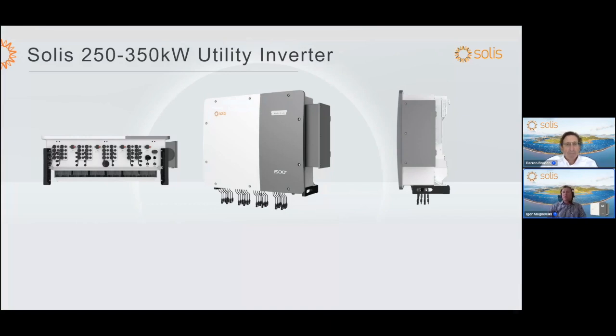We introduce here a slightly different version of this inverter using pigtails, where we combine two strings inside the inverter to each MPPT. So basically you have 12 MPPTs and 12 inputs coming in. This improves the wiring in the field, where you just need to bring in 12 positive and 12 negative wires to the inverter, instead of 24 positives and 24 negatives. It could be combined upstream with Y connectors, and basically with a single connection brought to the field.